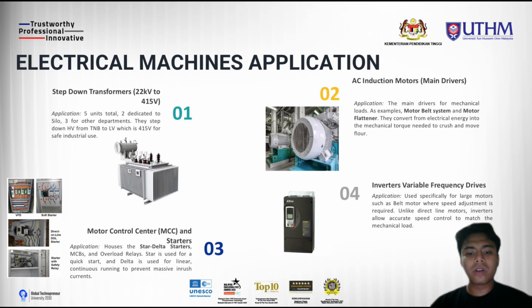So the third one is the motor control center, or MCC. This panel houses all the protection and control gear, specifically the star-delta starters, MCBs and overload relays. The star configuration gives the motor a quick start, while the delta configuration ensures smooth continuous running to prevent massive inrush currents. So lastly, we have inverters, or variable frequency drives.